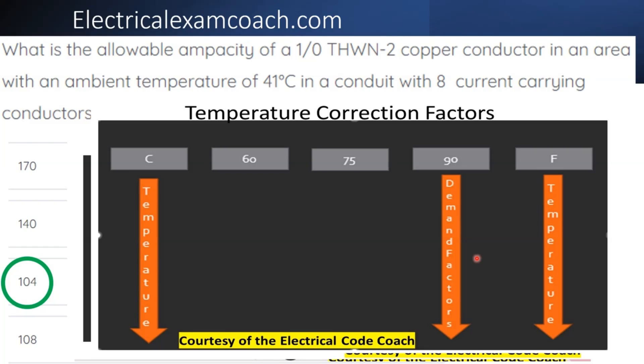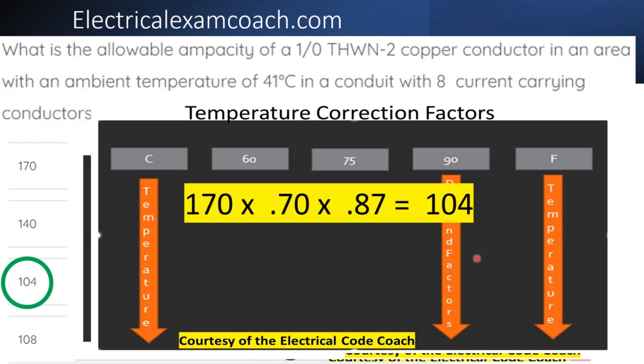Then we line up our math. Our original ampacity was 170 amps. We multiplied it by 0.70 and multiplied it again by 0.87, ending up with approximately 103.53 amps. In my opinion, we would round up to 104 amps. Let's get to it.